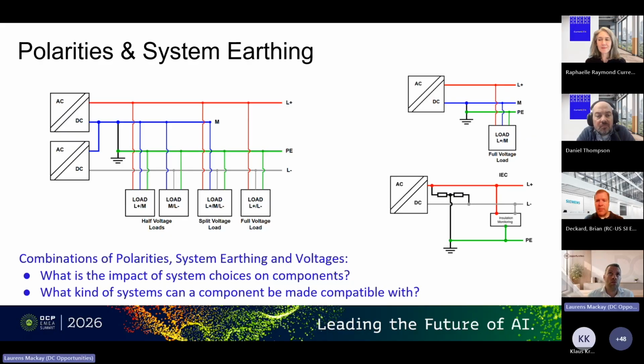In three-phase power systems, which are more dominant in the IEC world, you typically have 230/400 volts AC, right? Single-phase devices at 230 volts are used for pretty much all the small stuff, and big things you can connect to a three-phase load. In some cases, you can leave away the neutral conductor as well, right? If you have a factory with a lot of motor drives, it's very common to distribute only the phases, and that's the same thing we can do here. And coincidentally, this three-phase 400 volts AC gives you the same amount of power with the same current capacity in your conductors as the 700 volts DC, but you just save one conductor in the DC system. Awesome, thank you.